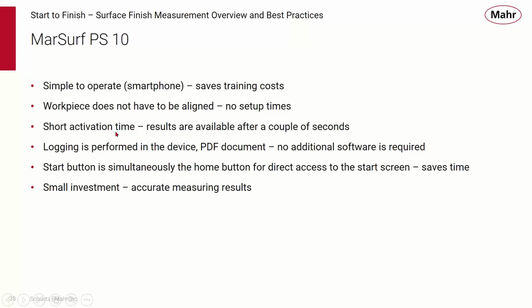So the whole concept with the PS10 is a simple to operate system like a smartphone. It saves in training costs. It helps because the workpiece does not have to be aligned so critically, so there's no complex setup times. It has a very fast response. You're able to get results in seconds. Logging is performed on the device in the form of a PDF document, so there's no additional software required. You can make the PS10 act like a memory stick, plug it into your PC, and you'll see PDF forms for each of the measurements that you've made. It's really a small investment for some very accurate measuring results.